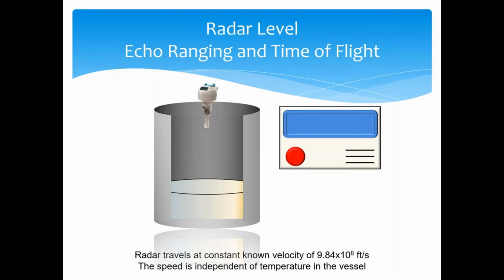So now if we switch gears to radar, radar and ultrasonic both work off time of flight measurement. You're still taking a signal and sending it from the transducer, or in this case the horn of the radar. It's going down, reflecting off the level in the tank, and coming back up. We're measuring the amount of time that takes to happen. There are two key differences here. The first is that this is a radar wave, as opposed to an ultrasonic sound wave, which travels at the speed of light through whatever media is in here. It does not have to be air.